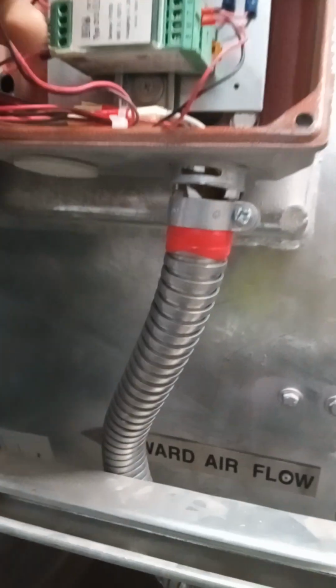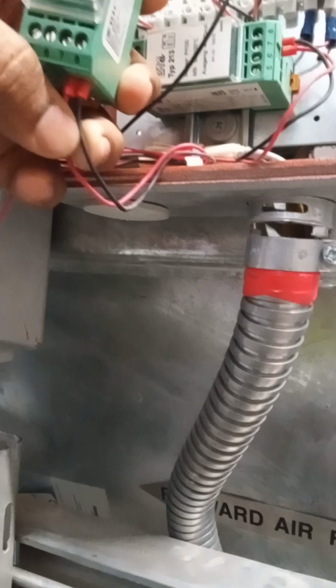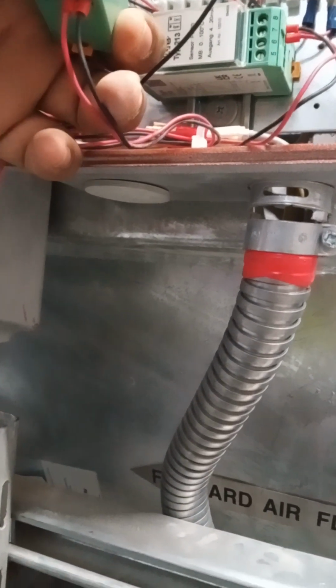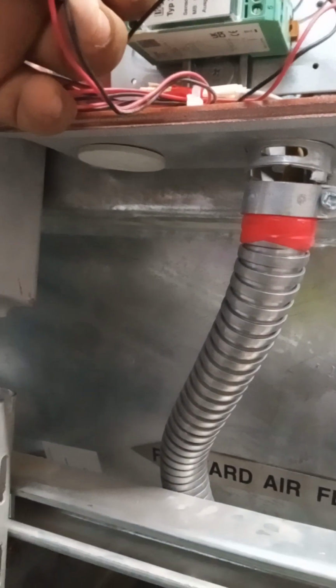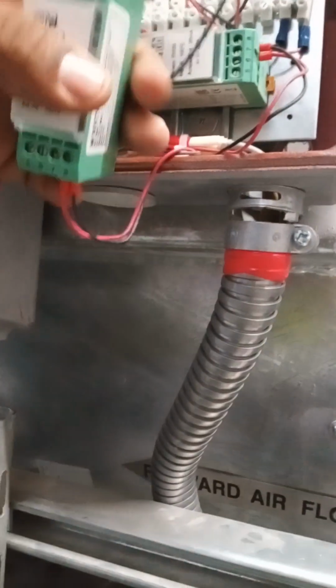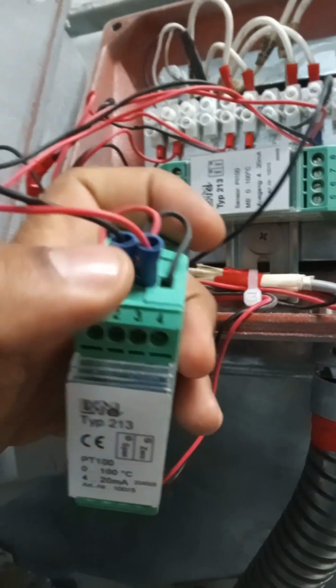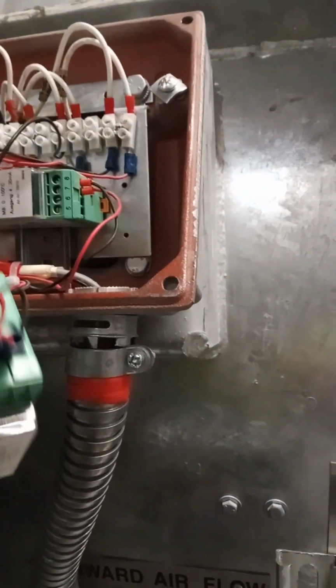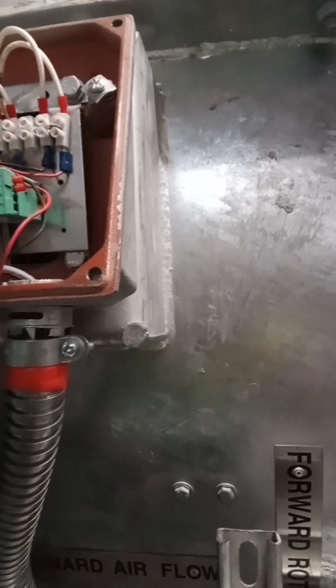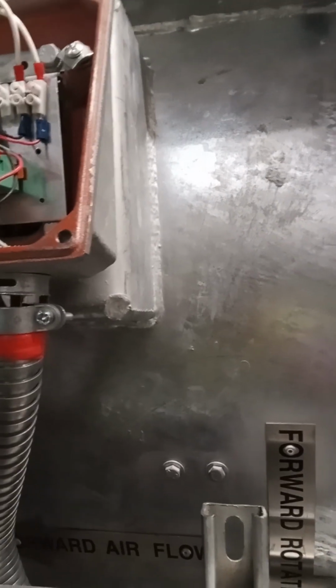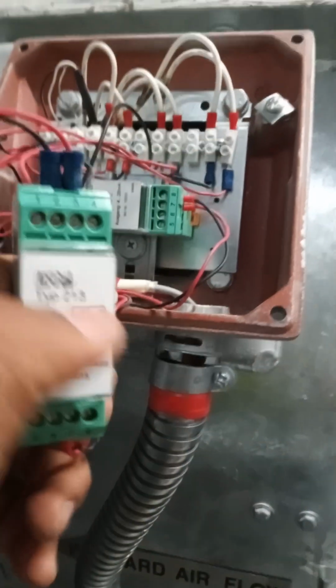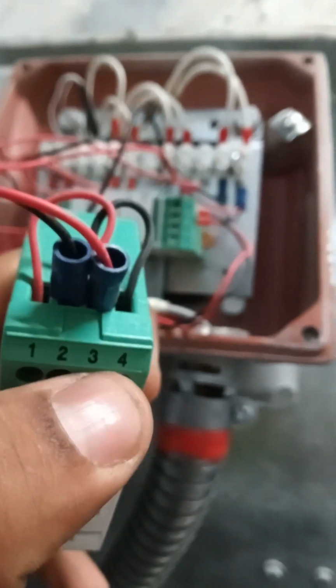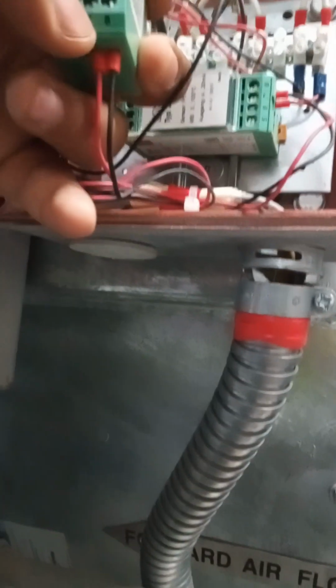This is the BMS cable, and this is one cable. This red cable is milliamps, going to our analog channel. This black cable is 24 volts from our BMS panel. And here the field side termination 2 and 3 is going to here, 2 and 3. And see, the other two, 1 and 2 are shorted, 3 and 4 shorted. 1 and 2 shorted, 3 and 4 shorted.